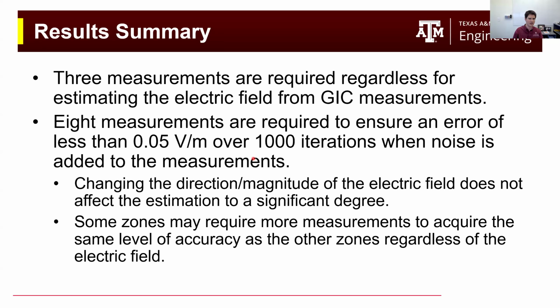For example, a logical choice would be placing GIC measurement devices at transformers more likely to see higher GIC, so you get a higher signal to noise ratio. But what if this transformer only has high GIC flows for certain storm types? What happens if there's a range of E field angles that cause low GICs on this transformer? These are questions we're working on answering.